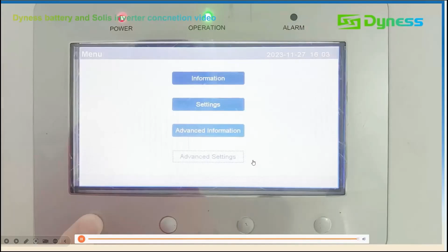Okay, this is about the Dyness and Solis inverter setup. Okay, and here I made some screenshots from the Solis screen, and there is another point our installers may pay attention to. That is how to check whether the battery and the inverter communication is normal. From this page, the control parameter, once the communication is normal, it will show the maximum discharge current limit and the charge current limit.